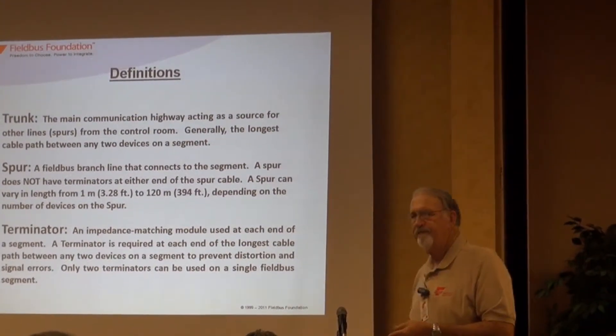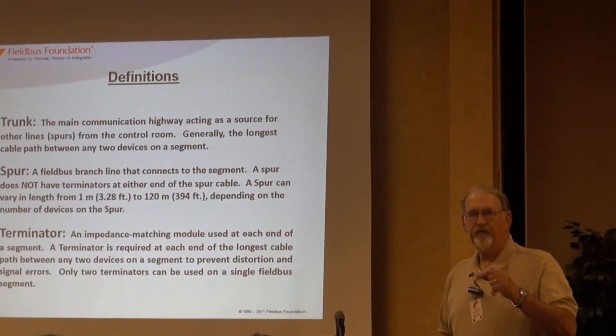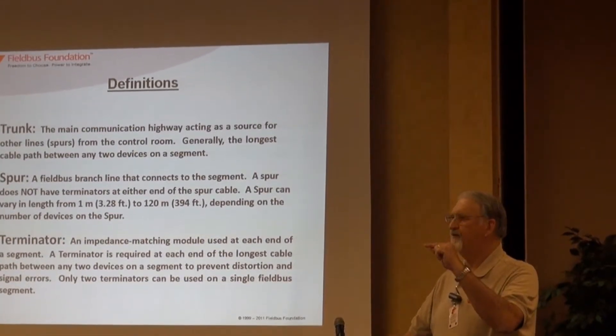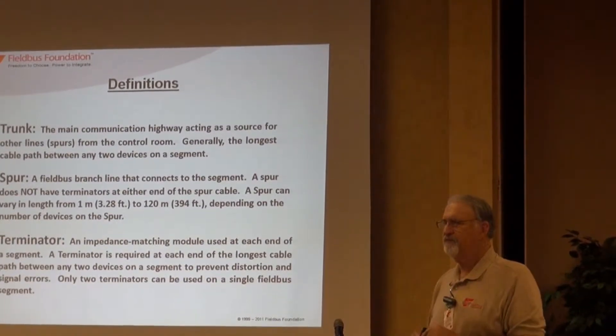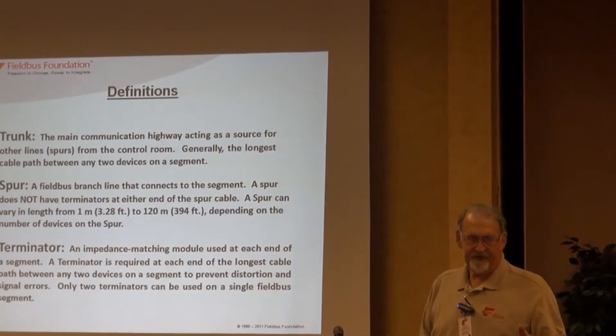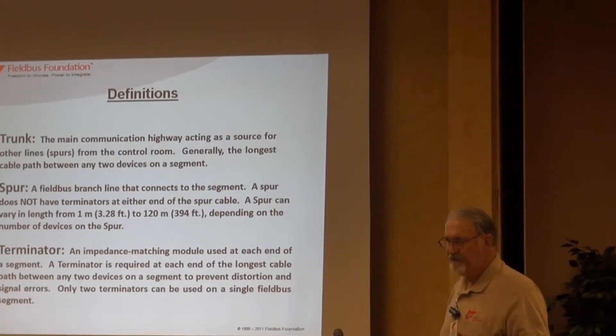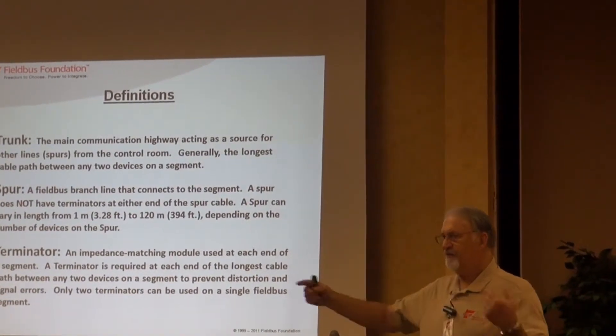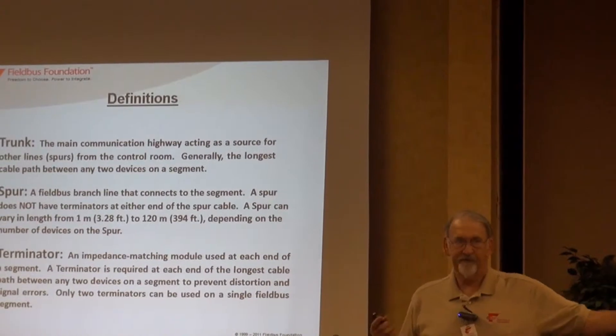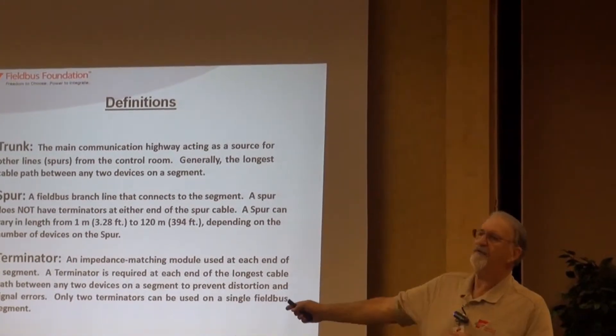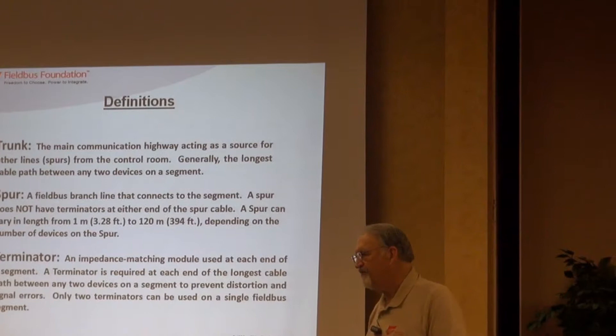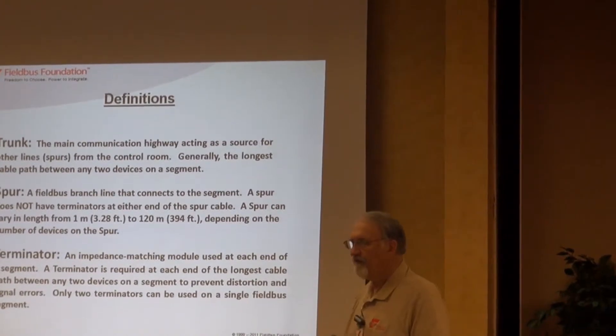A spur is the wire that goes from that device coupler out to a device. It has some length limitations on it. If you make a particular spur longer than your trunk, guess what that becomes? The trunk. So you have to act accordingly.